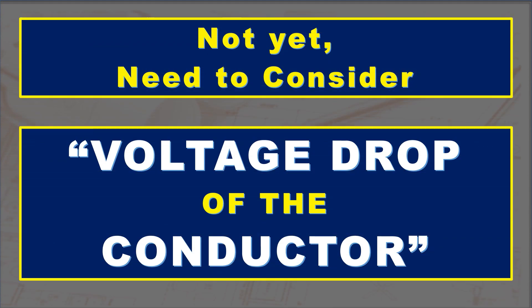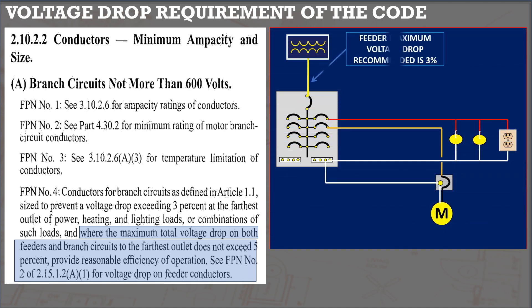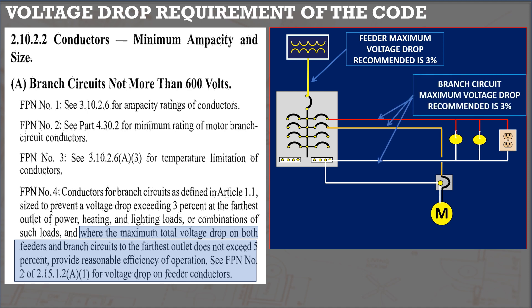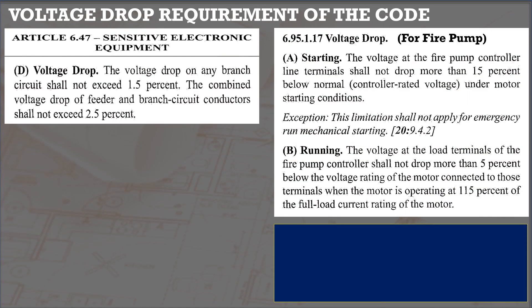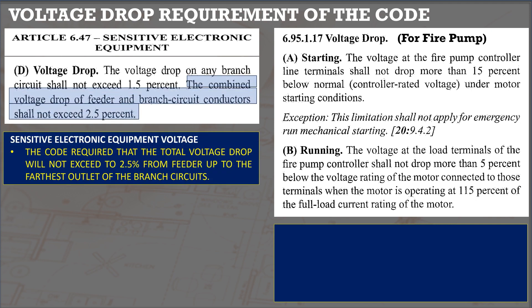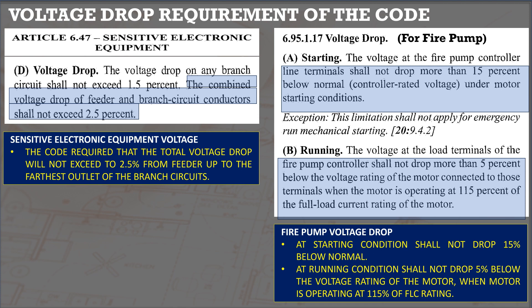This is voltage drop of the conductor. As stated in FPN4 of Section 2.10.2.2, it is recommended that the total voltage drop from the feeder is a maximum of 3%, same with branch circuits, and the total voltage drop shall not exceed 5% from feeders to the farthest outlet. Though not mandatory for branch circuits and feeders, this helps improve performance and efficiency. For sensitive electronic equipment, the total voltage drop shall not exceed 2.5%. For fire pumps, the voltage drop at starting shall not drop 15% below normal, and at running condition shall not drop 5% below voltage rating at 115% of full load current.